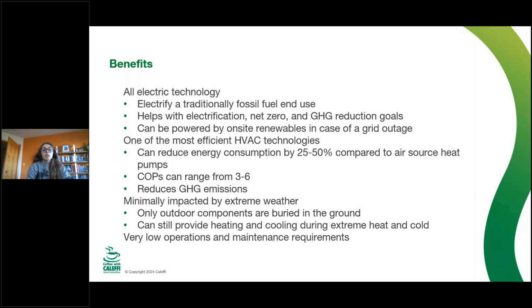They're also one of the most efficient HVAC technologies out there. They can reduce energy consumption by 25 to as much as 50% compared to an air source heat pump. And I did get a pre-submitted question about their efficiency compared to a more traditional HVAC system, like a furnace or a boiler. I'll get into that more in the case study, but these really are cream of the crop in terms of efficiency. This is going to be probably your best performing HVAC system in terms of efficiency, with COPs that range from 3 to 6. And because they are more efficient, you're going to help with reducing greenhouse gas emissions as well.